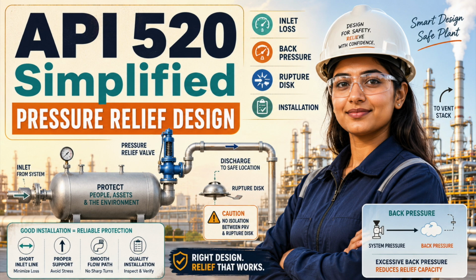A pressure relief valve can be correctly sized, properly certified, installed on the right vessel, and still fail as a protection system. That is the uncomfortable truth behind API 520, and it is where serious engineering begins. You are not designing a valve. You are designing an emergency pressure release path that must work during the worst credible event after years of operation under real process conditions, with real piping losses, real back pressure, real fouling, real maintenance constraints, and real human intervention.